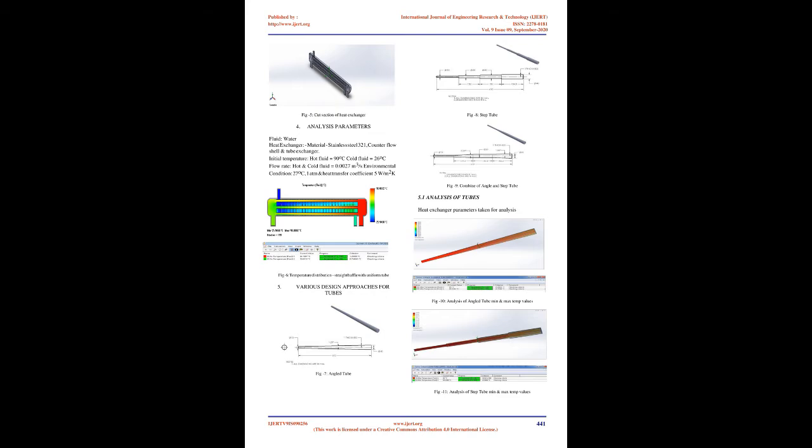Baffle spacing is of large thermodynamic concern when designing shell and tube heat exchangers. Baffles must be spaced with consideration for the conversion of pressure drop and heat transfer. For thermoeconomic optimization, it is suggested that the baffles be spaced no closer than 20% of the shell's inner diameter.